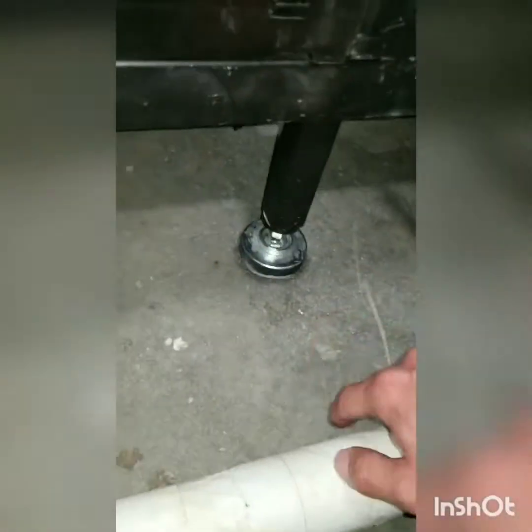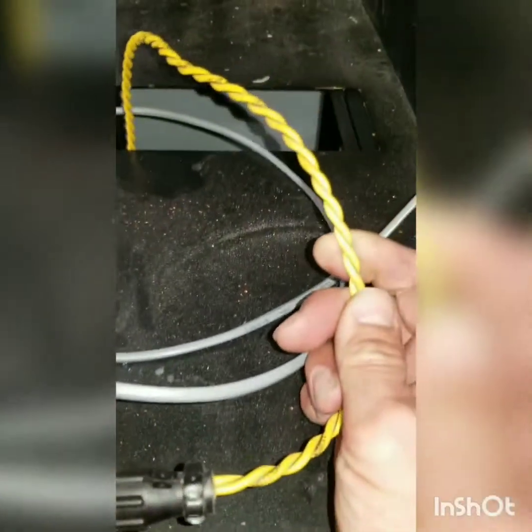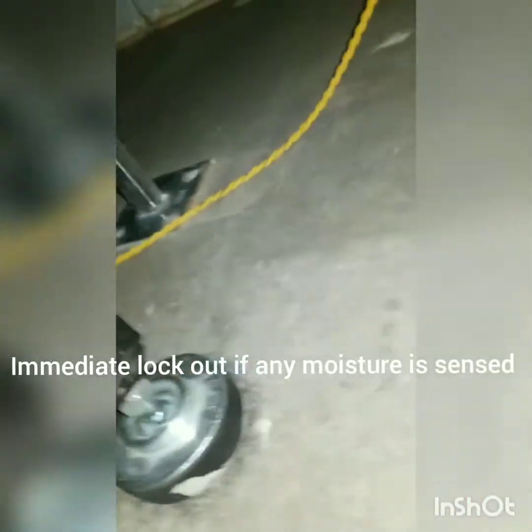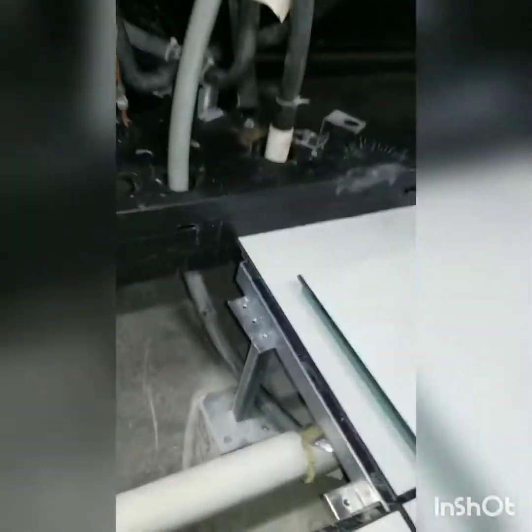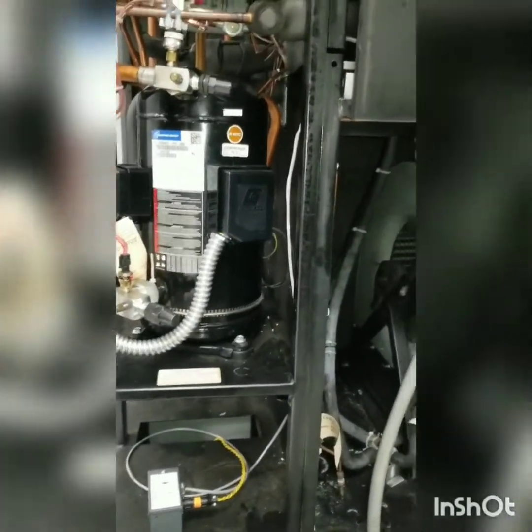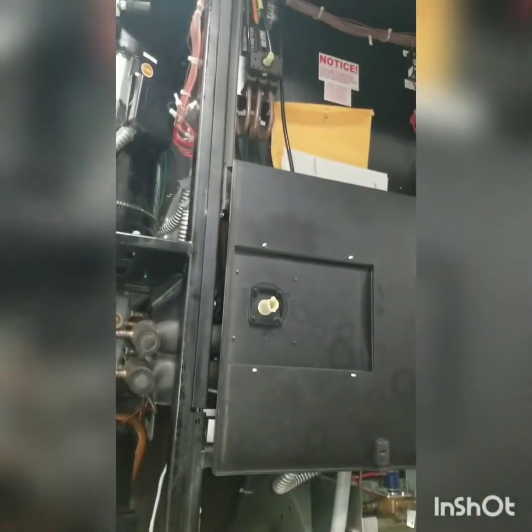We can get under the floor and see how our drain line comes through here. This is our wet switch, and they can be a pain to dry out once they get wet. These wires are coiled underneath — they just kind of hang out under there. So if they get wet, you can see how long it is — they'll be a pain. We're going to keep on going and get all our readings.